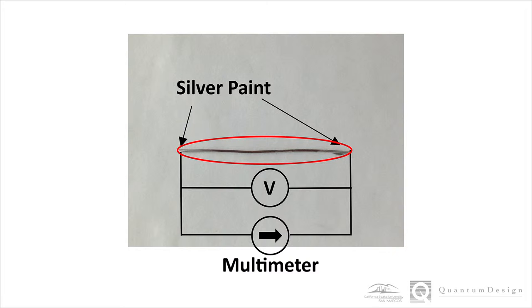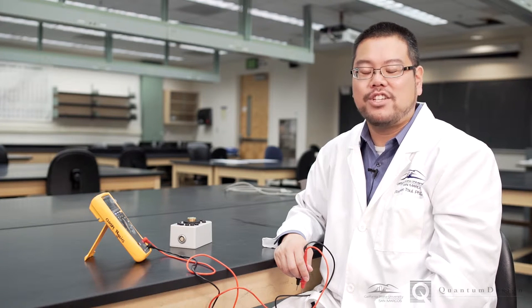Well, look at what's between the probes. It's not just copper wire. You have the wiring and also the silver contacts contributing to the measurement load. In other words, a two-wire measurement also picks up the contact resistance that's in series with the sample. So it's not a true characterization of the material.